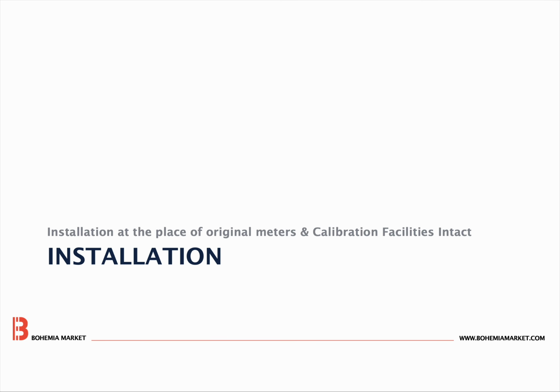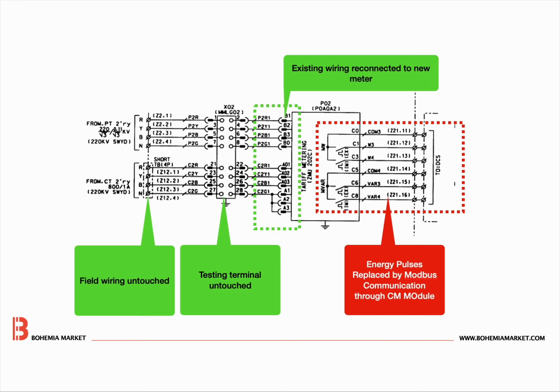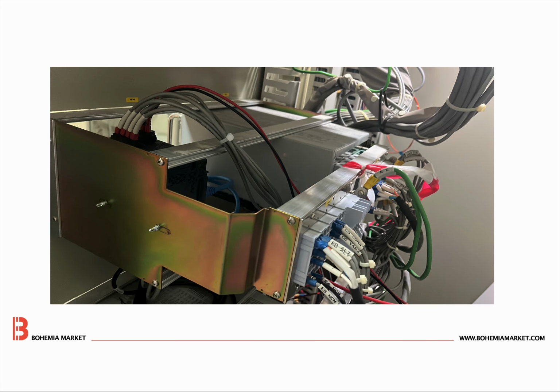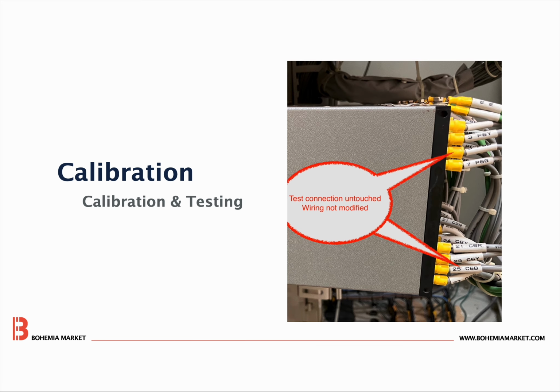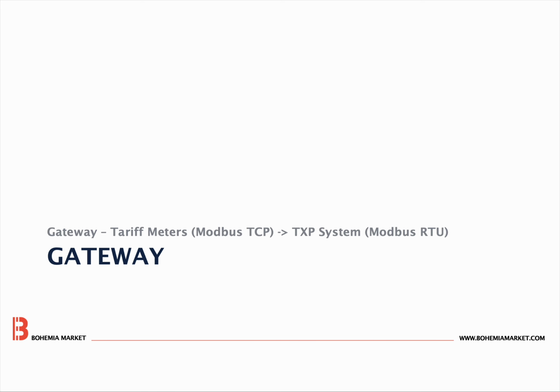Physical integration is just as important as data integration. Existing wiring from current and voltage transformers is reused. The same signals are split and connected to the new meters. No changes to CTs, VTs, or field wiring are required. The calibration equipment, or let's say connector, stays absolutely untouched.